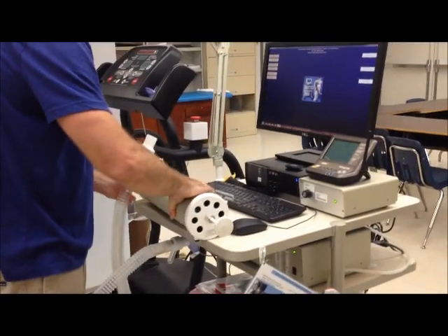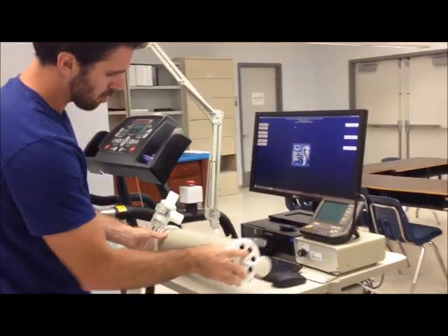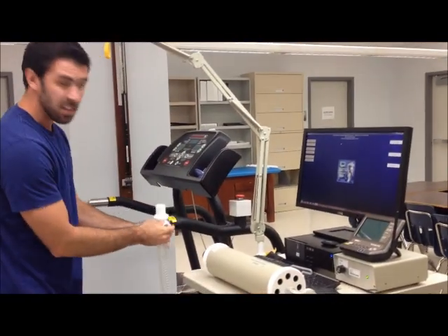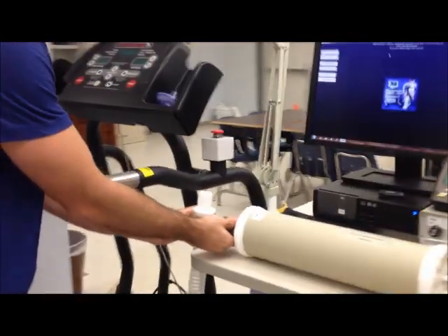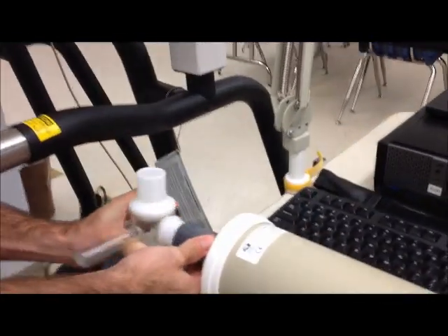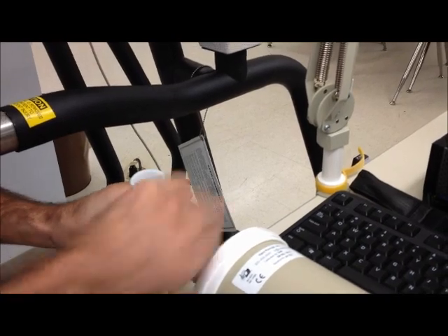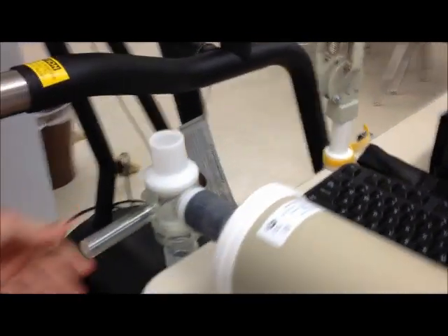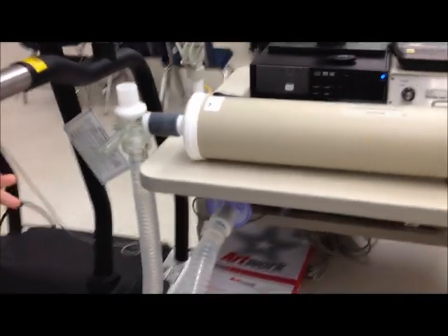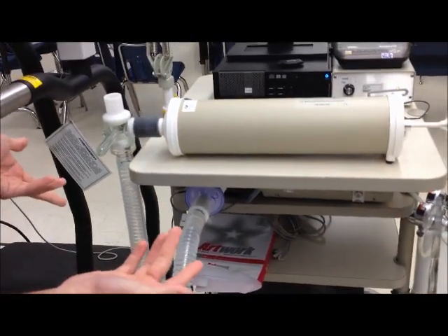Okay, and then from there, this is our 3-liter calibration syringe. Just set this right on the table. Now we're going to plug this in, like so. Make sure it's nice and snug. Make sure everything's tightened well. And this is the setup for Flowmeter calibration.